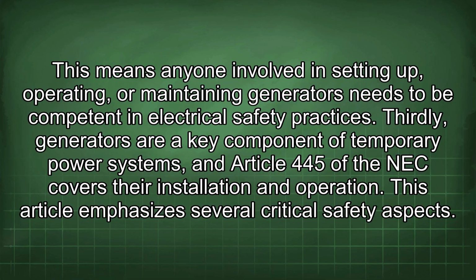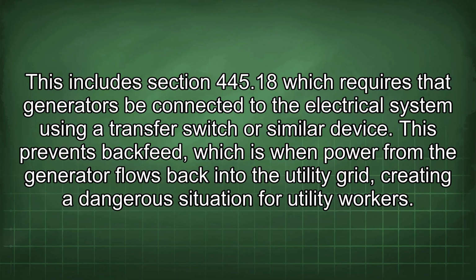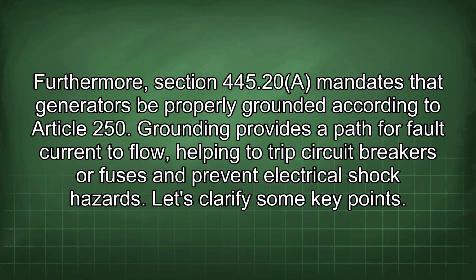Thirdly, generators are a key component of temporary power systems, and Article 445 of the NEC covers their installation and operation. This article emphasizes several critical safety aspects. This includes Section 445.18, which requires that generators be connected to the electrical system using a transfer switch or similar device. This prevents backfeed, which is when power from the generator flows back into the utility grid, creating a dangerous situation for utility workers. Furthermore, Section 445.20 mandates that generators be properly grounded according to Article 250. Grounding provides a path for fault current to flow, helping to trip circuit breakers or fuses and prevent electrical shock hazards.